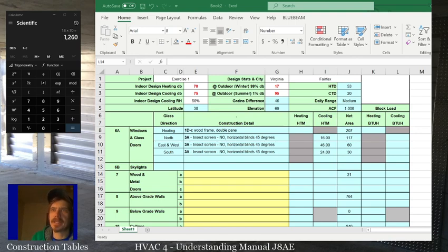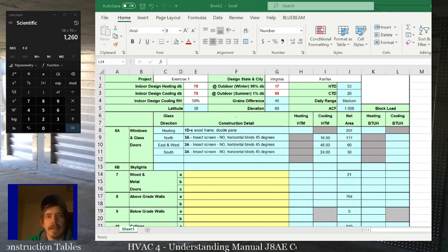But basically, because you have to account for the sun and other factors, radiant heat loads and everything else, you can't just use the straight up temperature difference. You have an effective temperature difference accounting for heat from radiation and actual temperature difference heat. And the default design temperature is always 75, and passive floors on cooling have basically no U value. We'll get there.